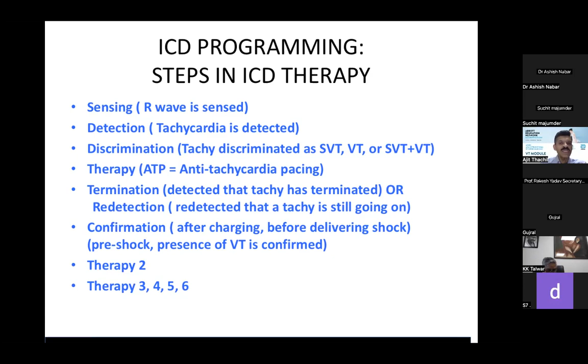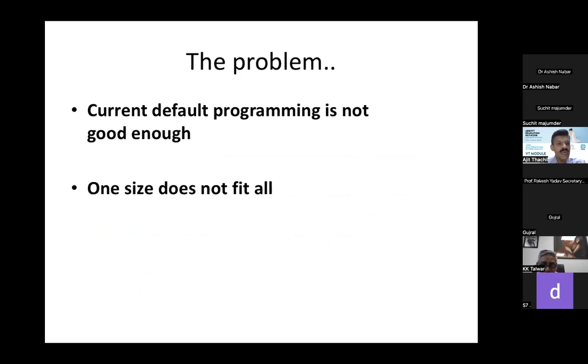Then it will start charging. For example, if it has to deliver a shock, it will start charging. After charging, just before delivering the shock, it will confirm that the tachycardia is indeed still going on, and then it will go on to deliver the shock. So this is the sequence in which the ICD works. The problem is that the default programming in the ICD does not work in most patients, so we really need to find the exact programming for the particular patient. We need to make sense of all these numbers, the numbers that we see on the ICD screen.